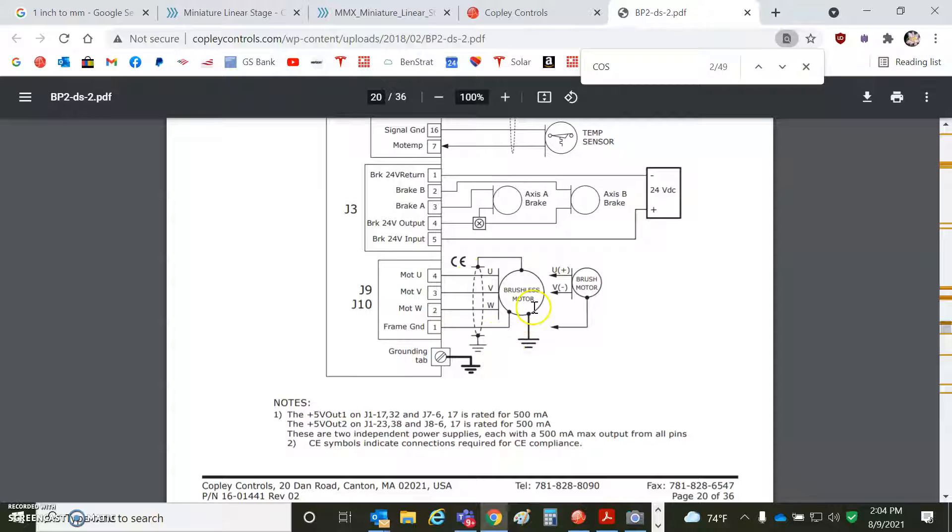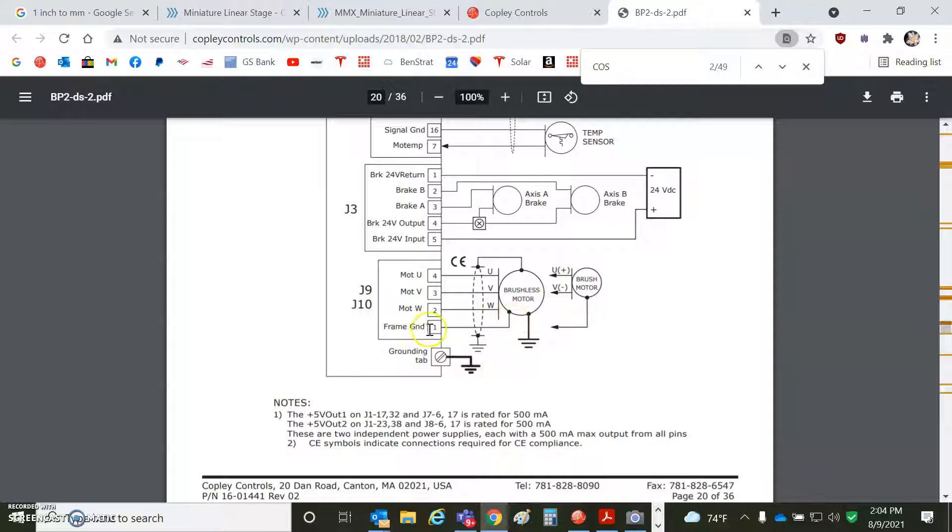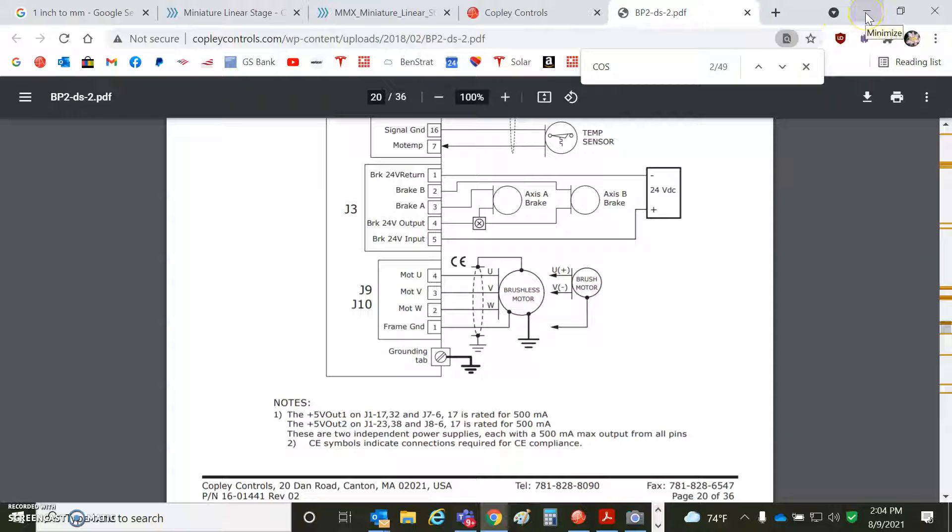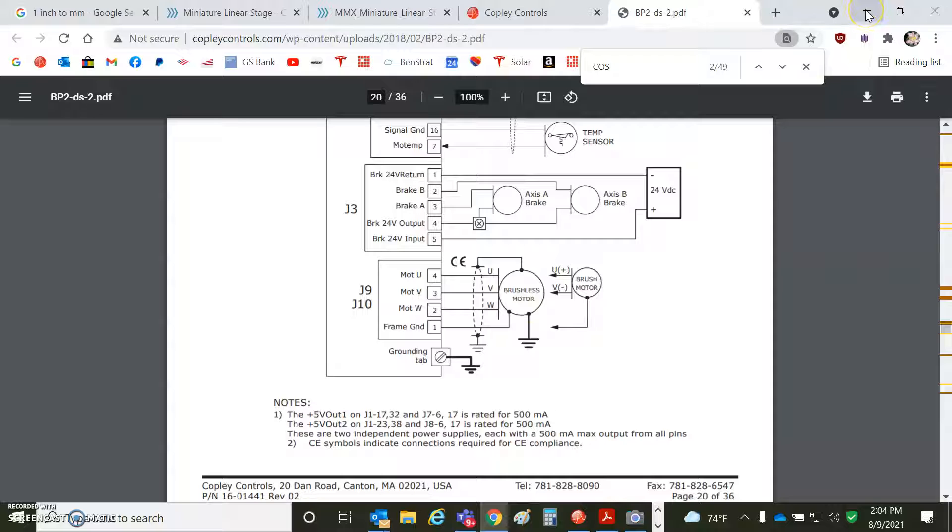You should directly connect the motor case to Earth or run another wire, like the frame ground wire. This motor only had two wires and they used the shield. But yeah, you saved the wire, but how good is that shield? It's probably okay. They're experts. They know what they're doing. It just seems wrong to me. So anyways, anything you can do to improve, put the motor case to Earth and that should nail it.